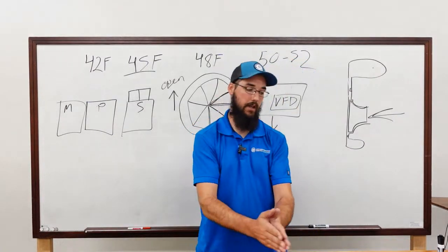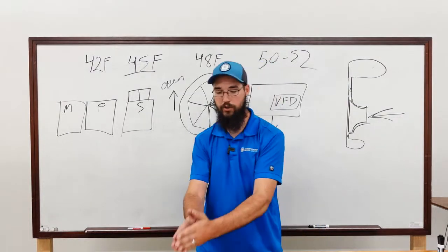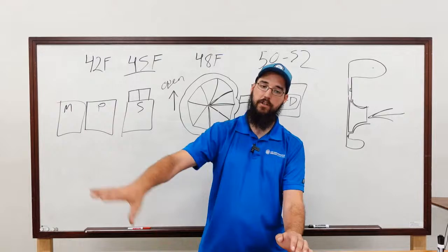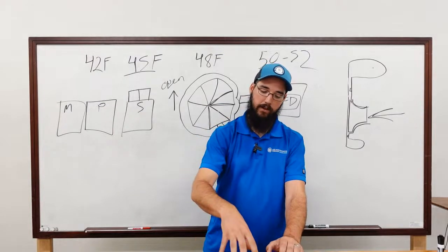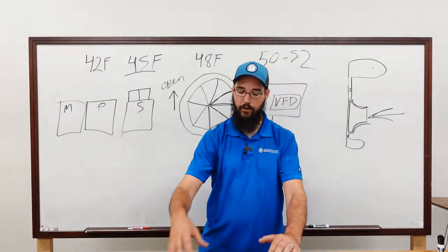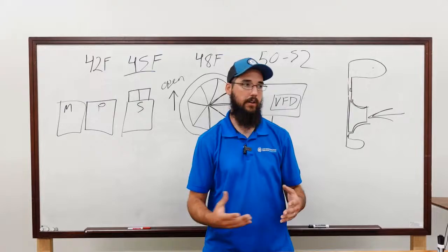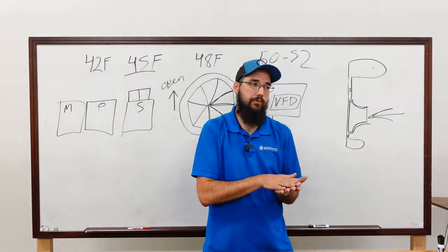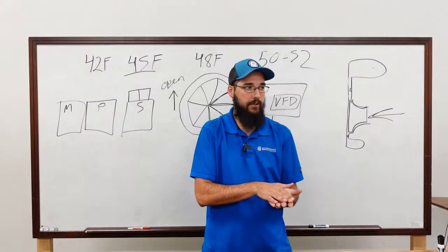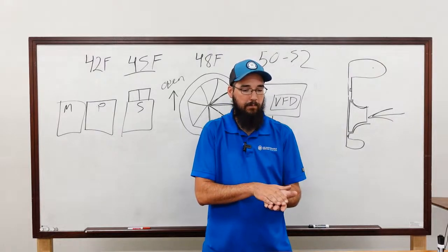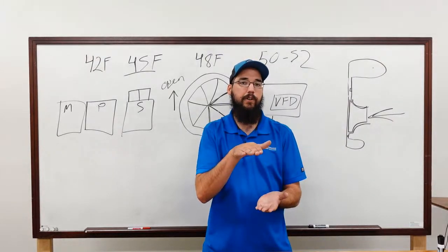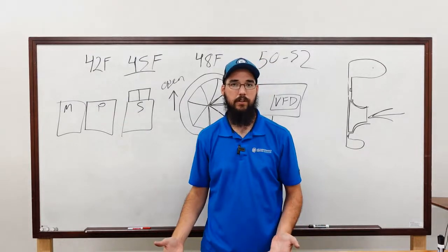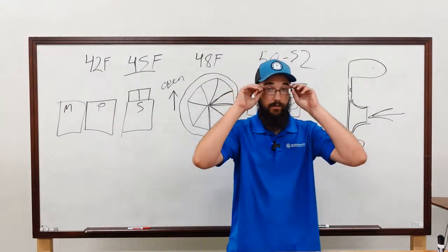Anyway, flow water. That applies to recovery or charging. Doesn't matter. Because in the same way, when you're charging the refrigerant back in, as you're charging it and everything's boiling off and trying to fill back up, you're still going to be below freezing on your saturation until you get enough refrigerant in there to build enough pressure to come out of a freezing condition. And that's when it's really dangerous.